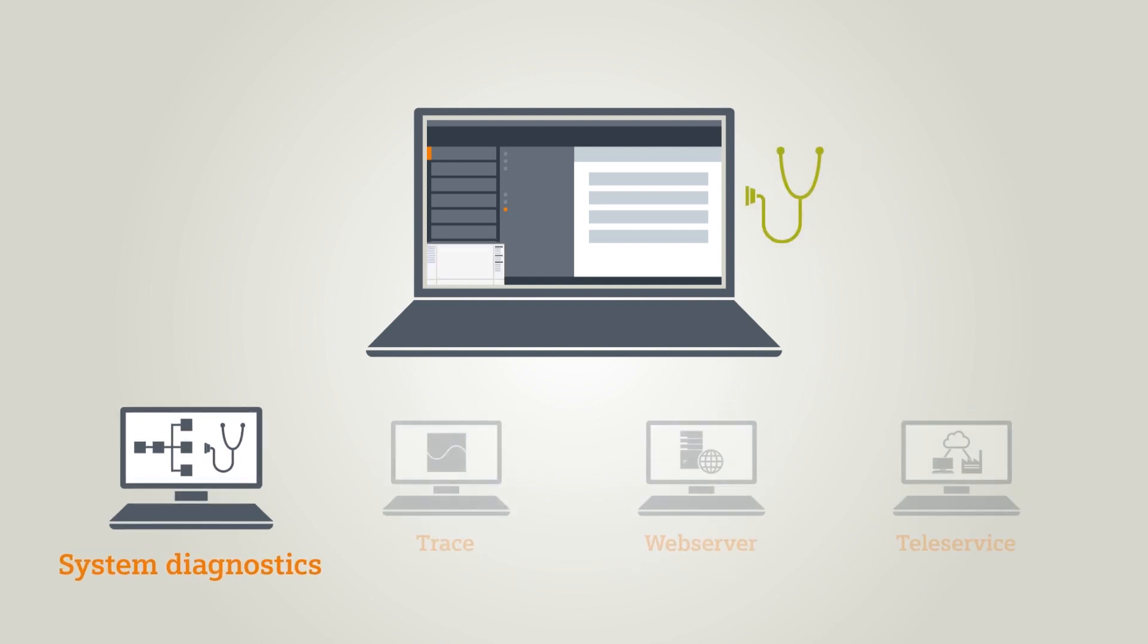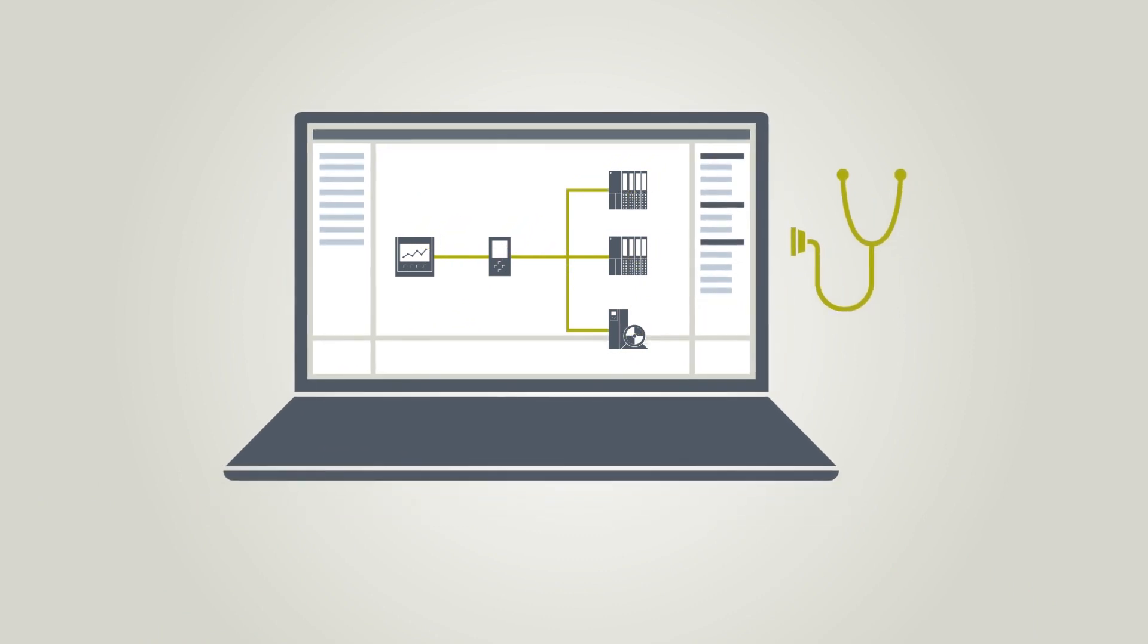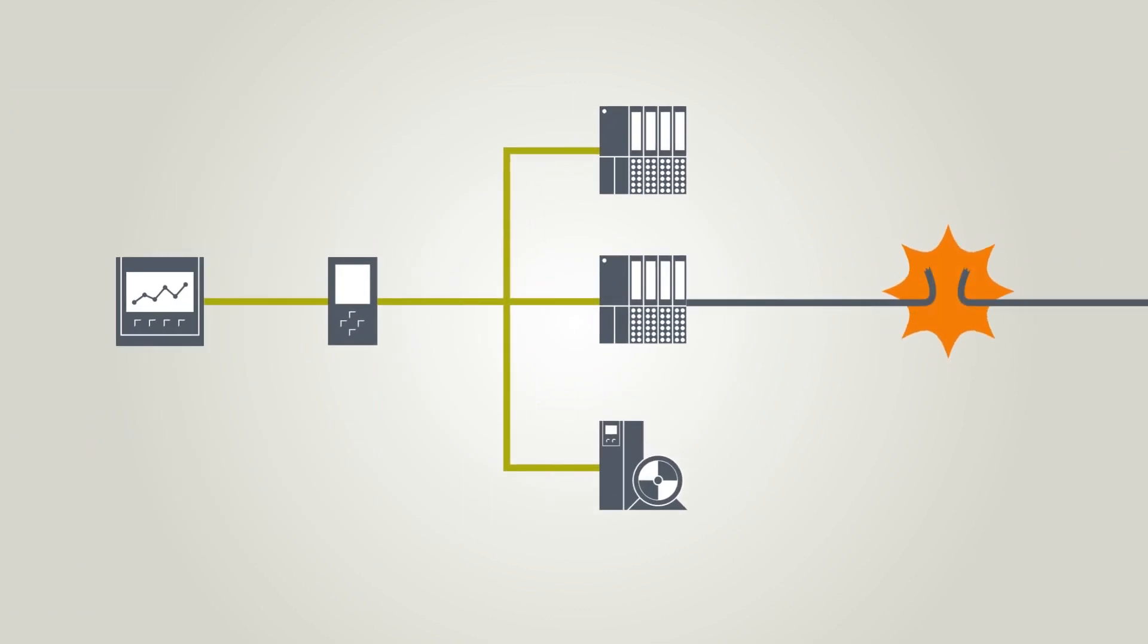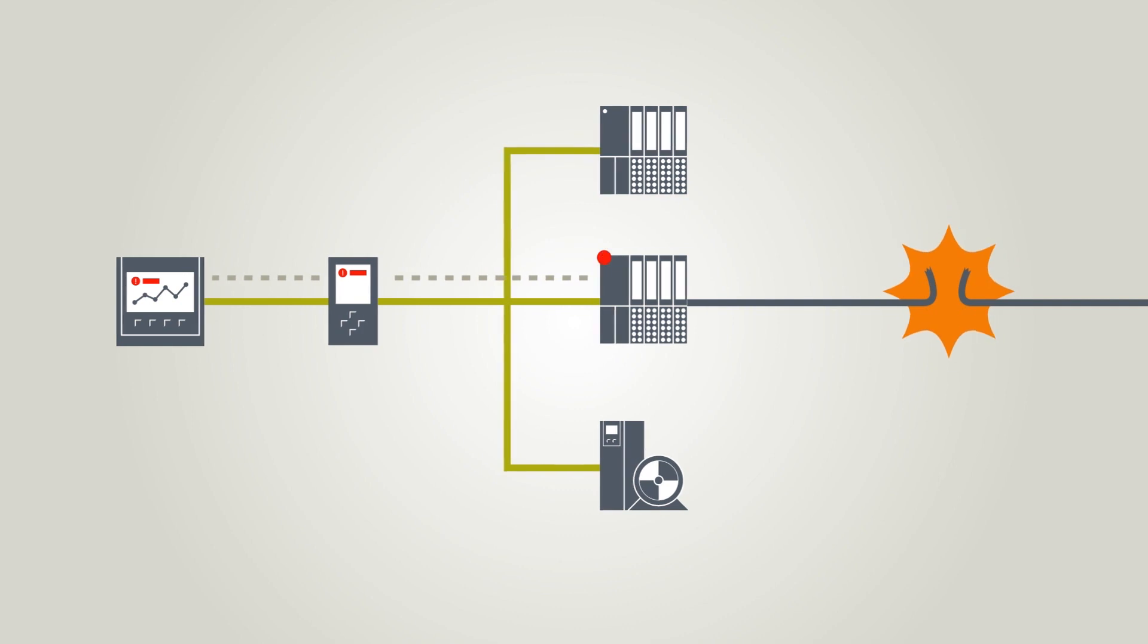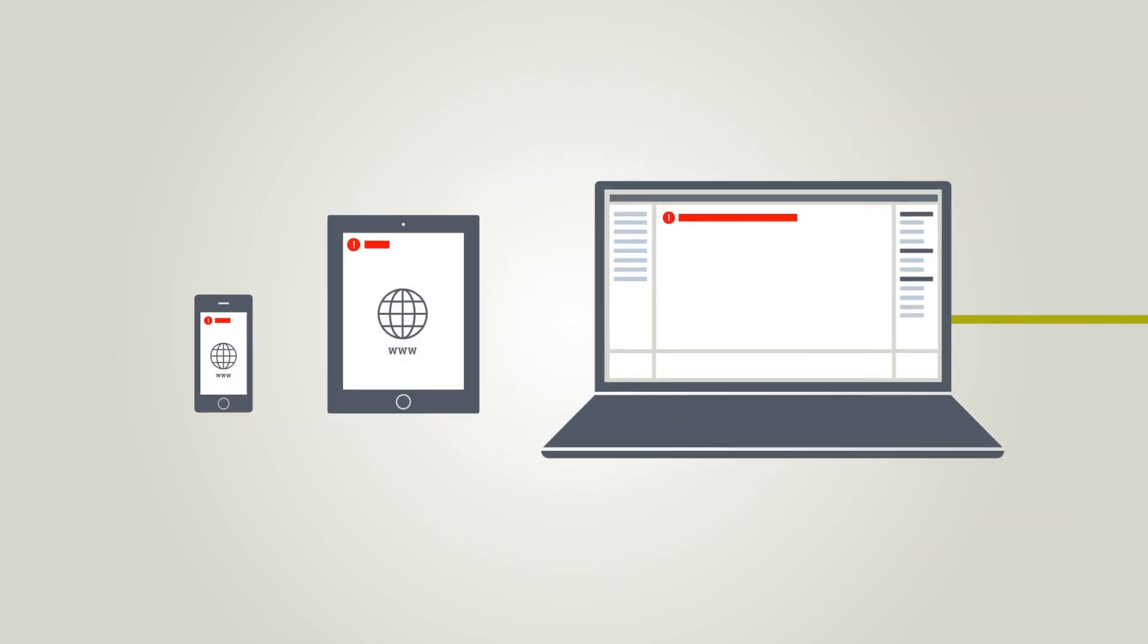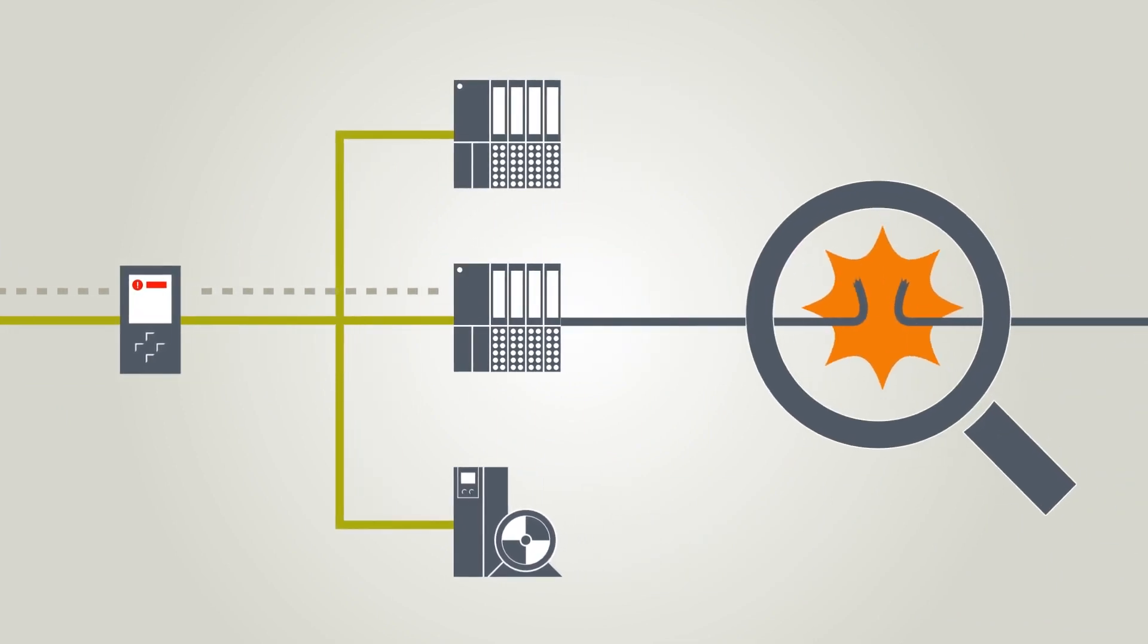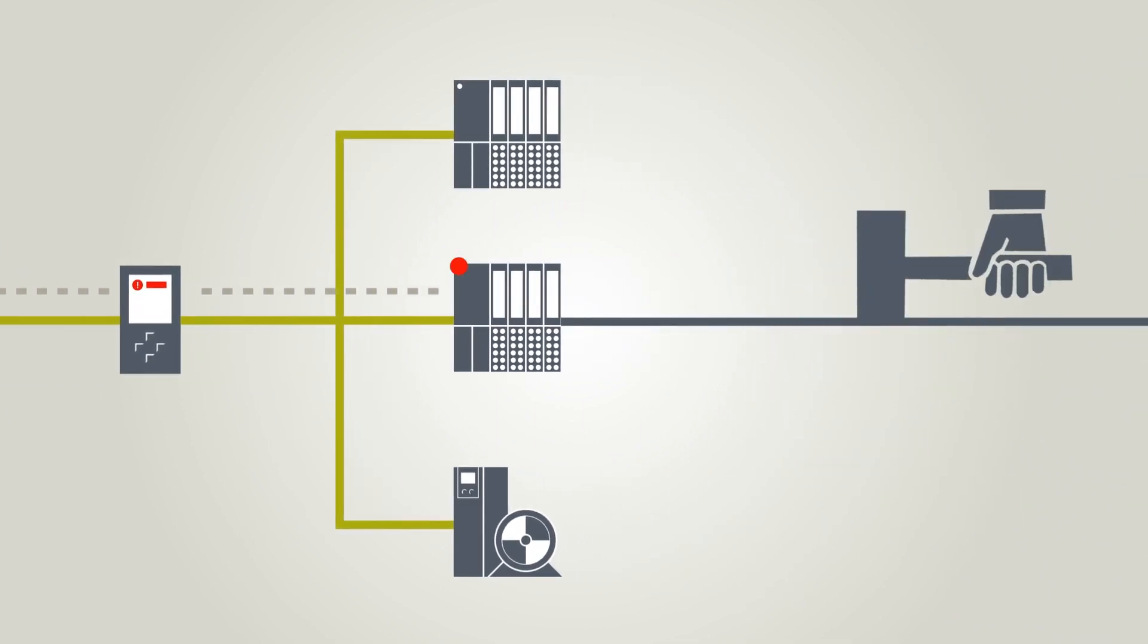The system diagnostics are automatically set up when a device is configured. You don't need to write even a single line of code. In the case of an open circuit, for example, the device automatically detects the fault and sends the diagnostics data to the assigned controller. The controller then displays the fault message on all the display media. This means that you can localize the fault very quickly and resolve it immediately.